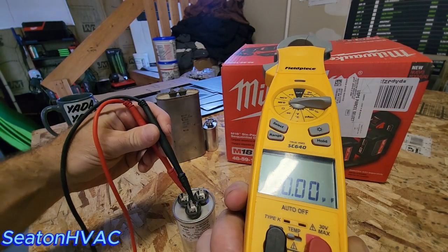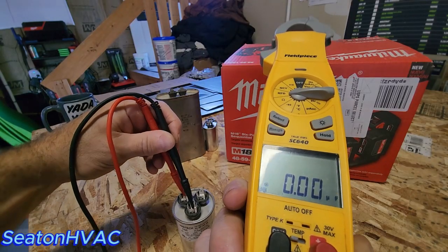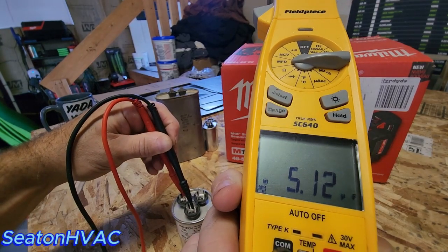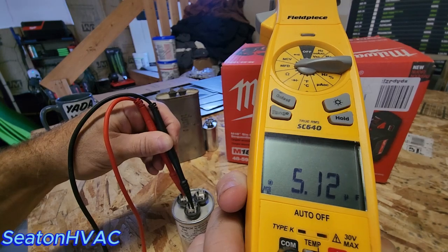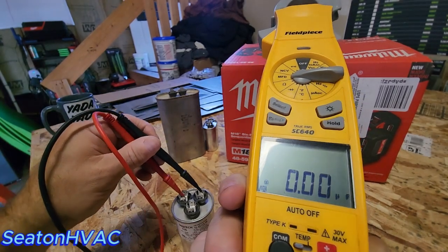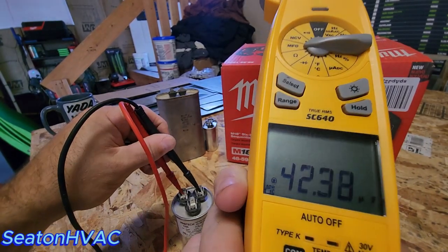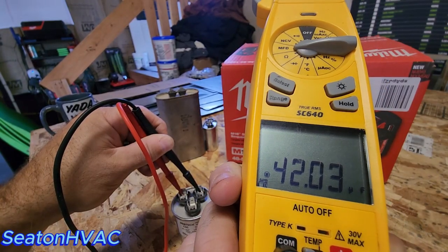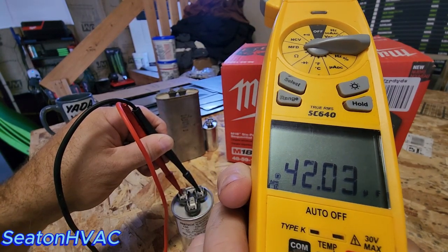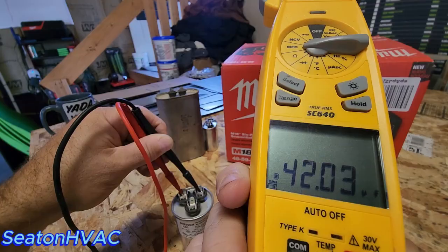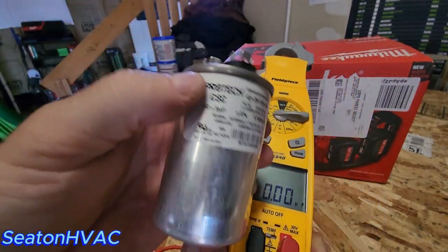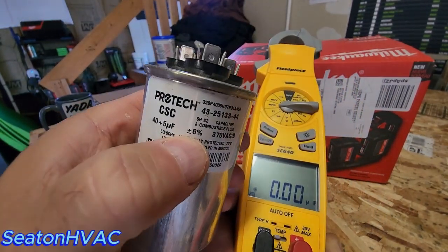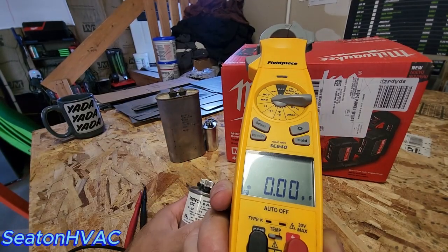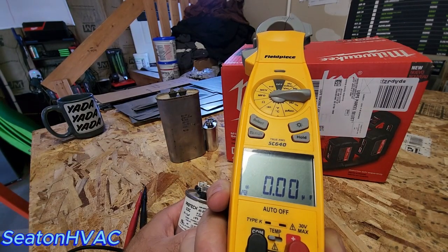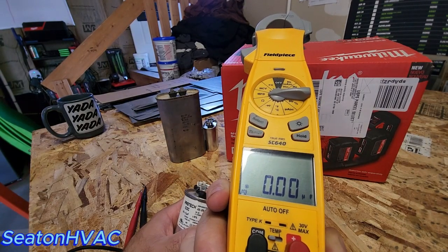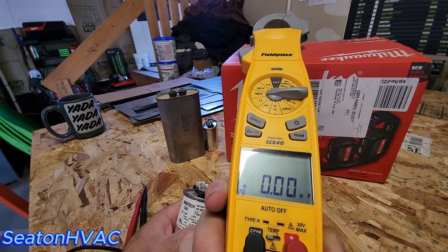Not enough coffee. So between common and fan, it reads 5.12, so we know that's good because it was calling for 5. And then we're going to go between common and our herm terminals, and that reads 42, so we're good. And that actually is almost a little high. It's got a 6. So another thing you'll see on these is they have a tolerance, plus minus 6%. So, you know, you figure out what 6% of 40 is. Top of my head, that's 1/6, you know, that's 2 point something.